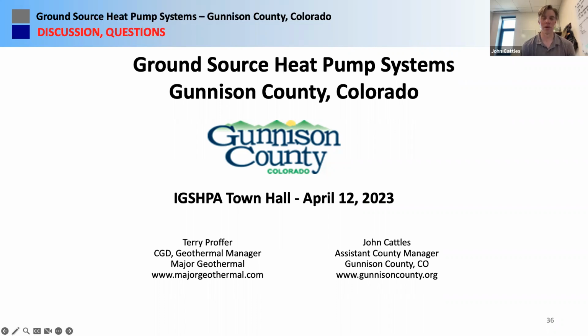It's just overly complex. What I've found in comparison to our distributed heat pump systems is that it's very, very simple. When we're able to do a distributed system with heat pumps matching zones, it simply runs off of a local thermostat. We do have controls monitoring that, and we control the pump, the loop systems, and our air exchange systems. But the controls complexity is orders of magnitude more simple, and therefore it just works more efficiently. It's easier to optimize and easier for us to maintain occupant comfort.